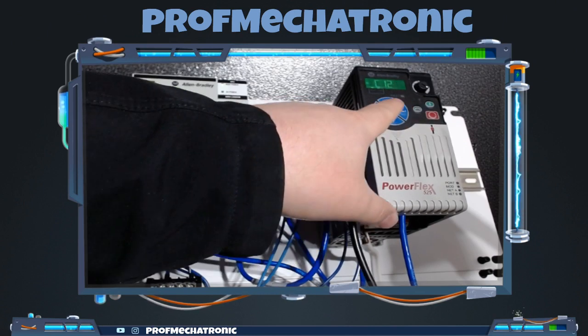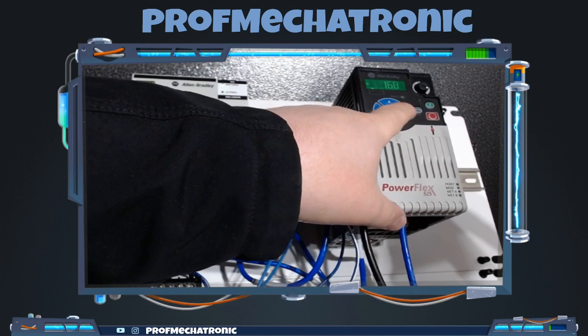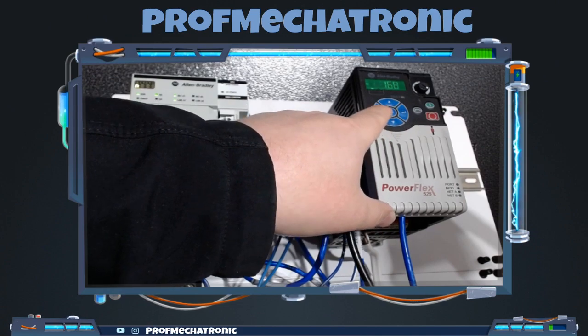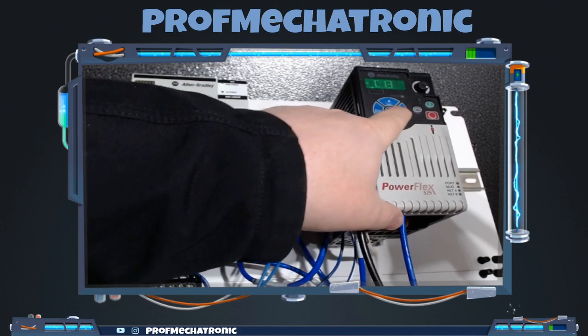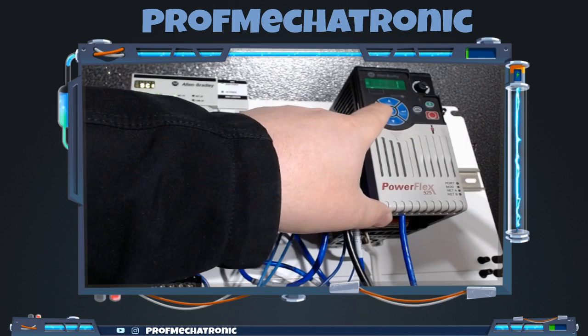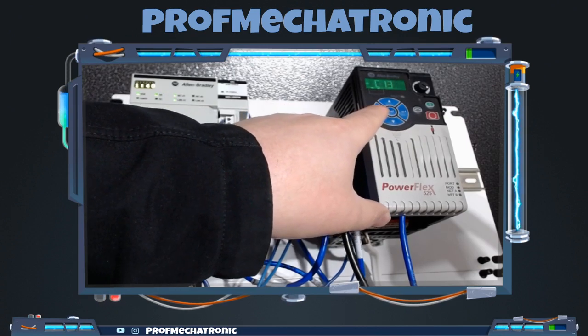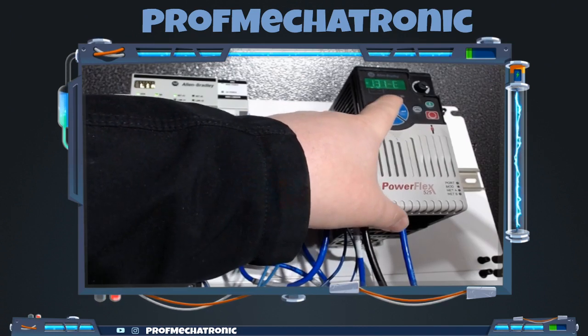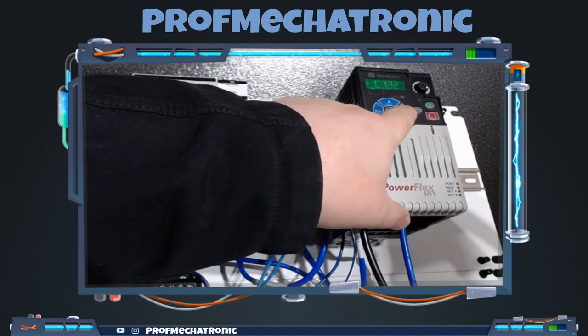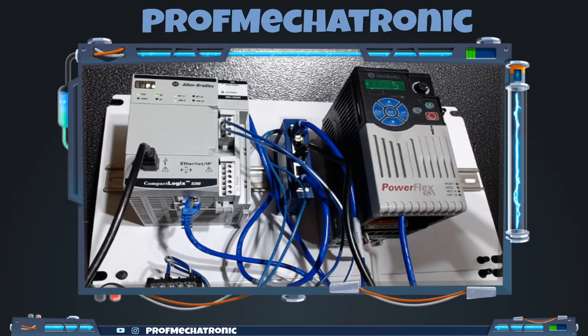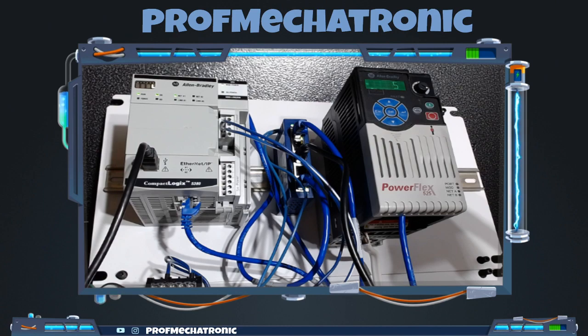We're going to go back and go to C130. C130 is set to 168, that's good. C131, we're going to look at that, it's set to 1, perfect. So now we have that set to our private addresses. We're going to check C132 now, that's the last octet. That's the octet we really care about because we can't have it be the same as anything else on the network, or there won't be any communication.